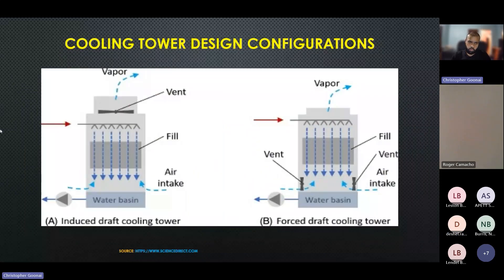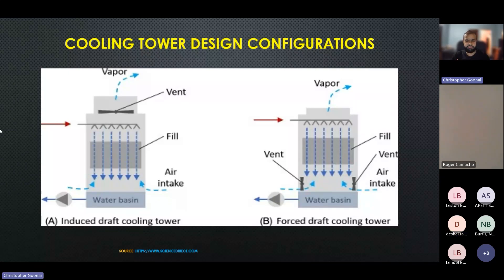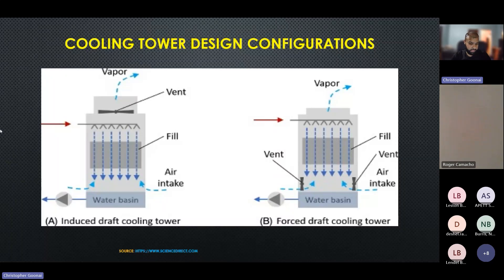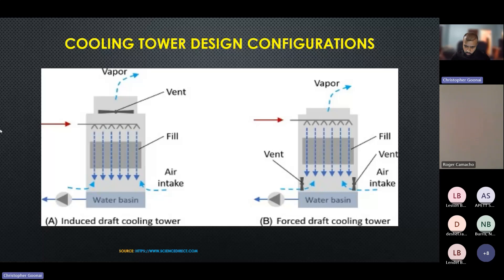Here we have the cooling tower design configuration. Again, you have the induced draft and forced draft for cooling towers as well, as well as the ACC — the air-cooled condensers. This is the cooling tower design; slightly different, but the fan makeup itself would not really change. On the left here we have the induced draft cooling tower, which is probably the more typical design you'll see throughout the industry. The forced draft uses blowers to force the air through the system and out the top.